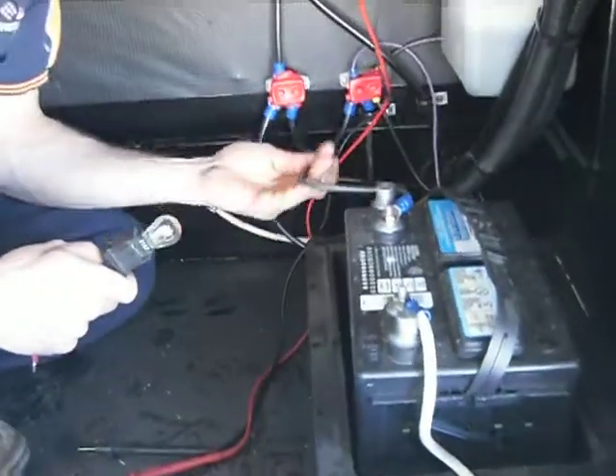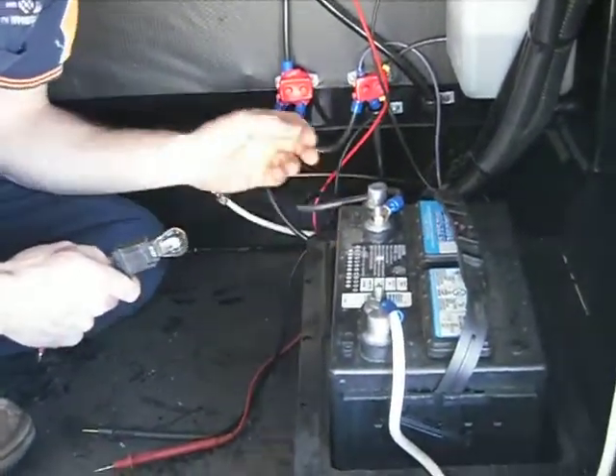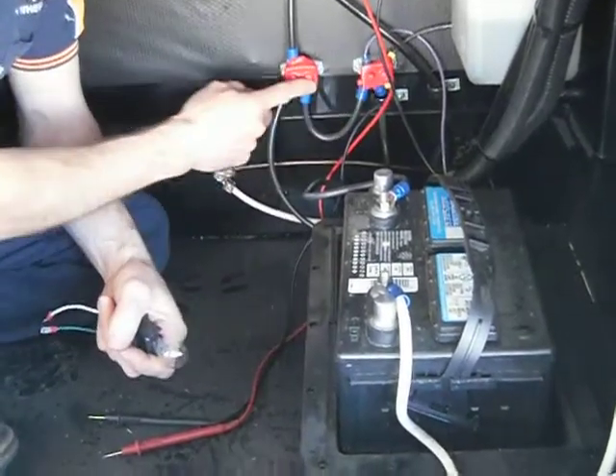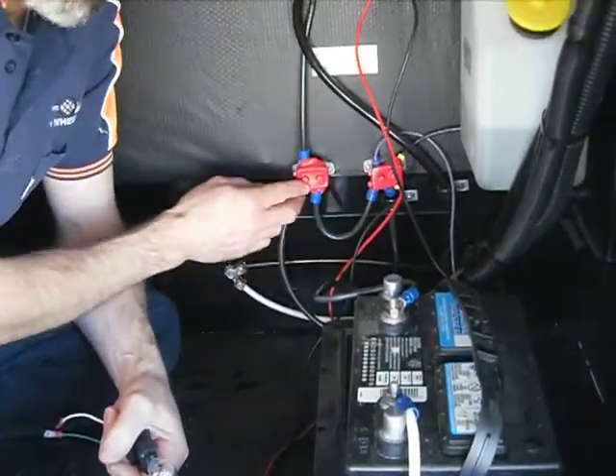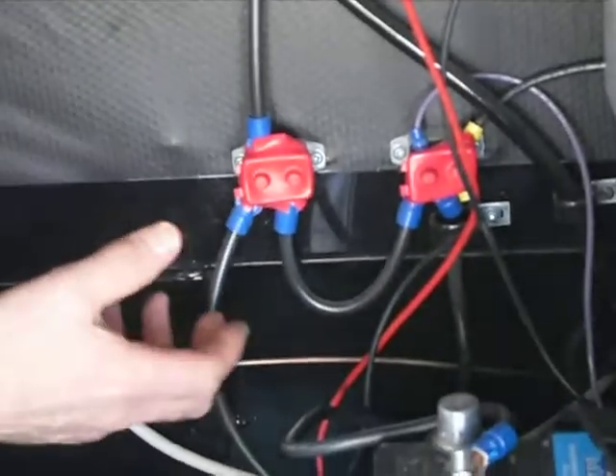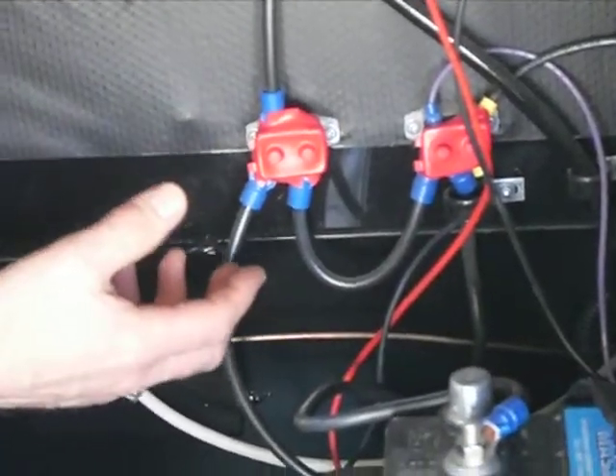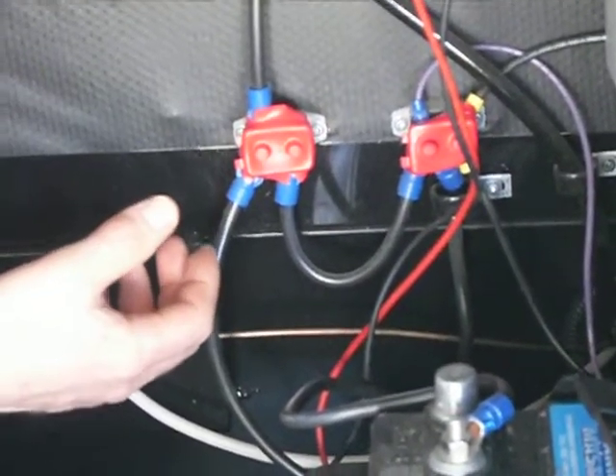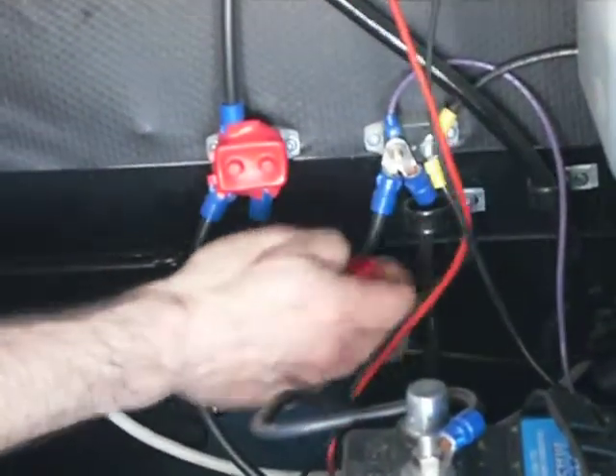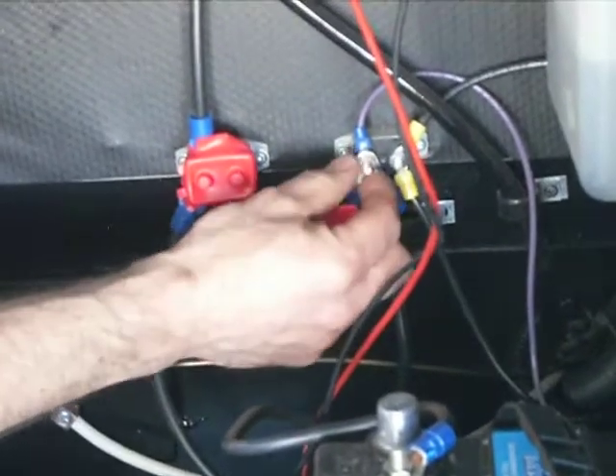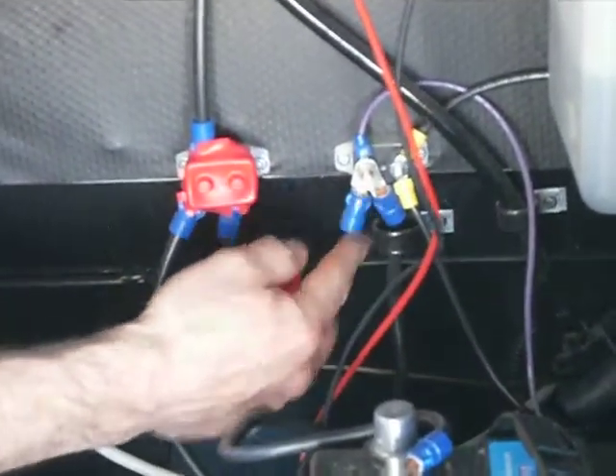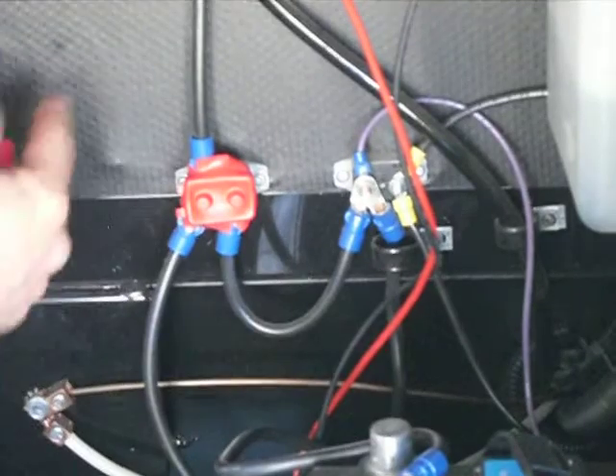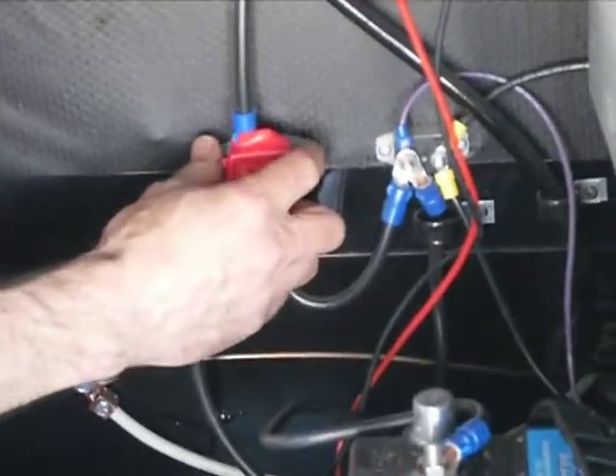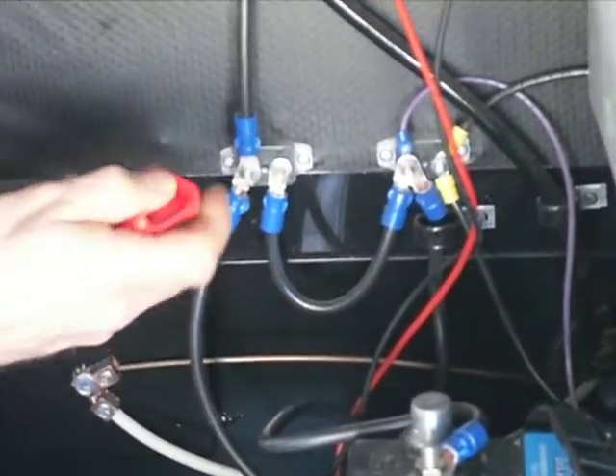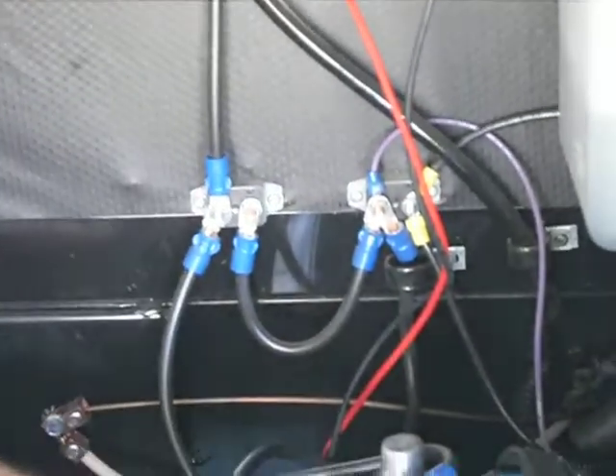And we have a positive terminal. The positive will then go to thermal circuit breakers. These are for heavier items in the van like the front legs or the slide outs. The wire will go directly to one of the posts, a little thread with a quarter inch nut on it, then loop to another one and so on, depending on how many thermal overloads you have. They could be rated at around 30 amps.